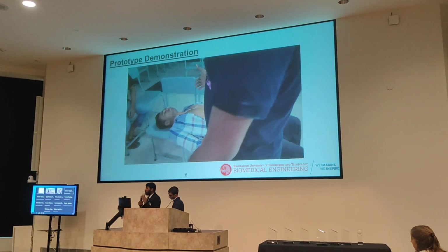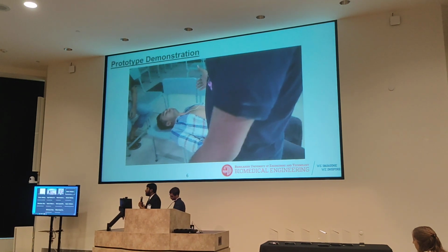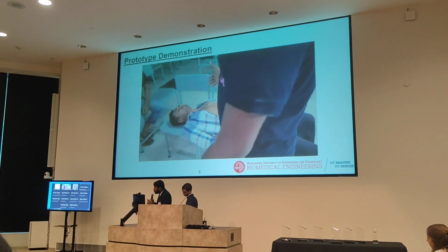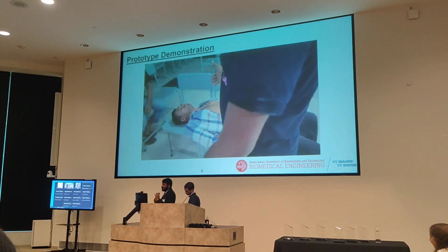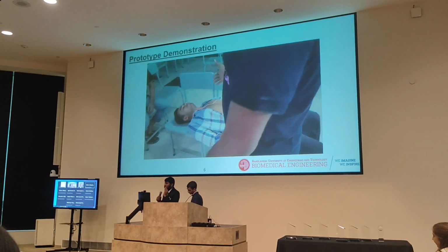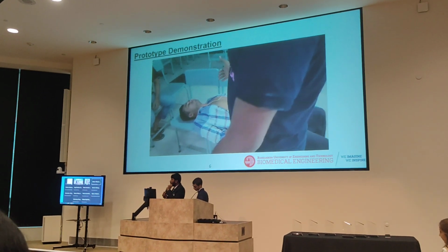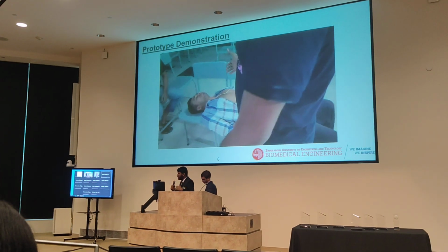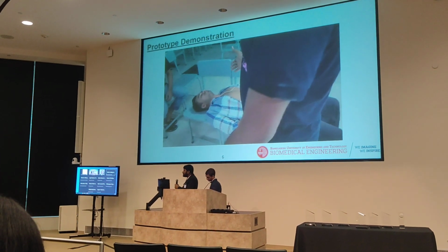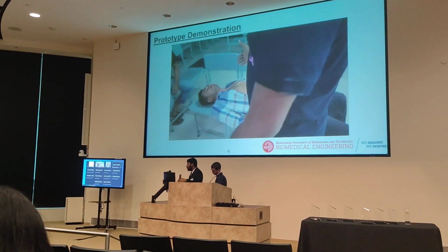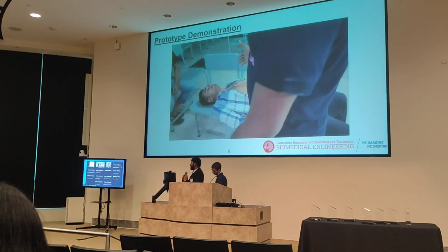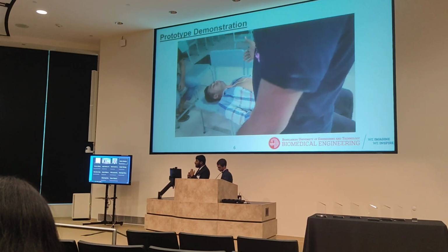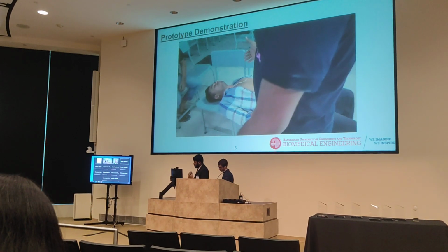Yes, I know that the traditional AED found in the local market has the sensor and the shock provider in the same pad. But since our main priority is to make it low cost, that's why we are focusing on this. It will not be a problem for countries like low income countries to use separate sensors, one for shock and one for collecting ECG, because our first priority is accurately saving life.